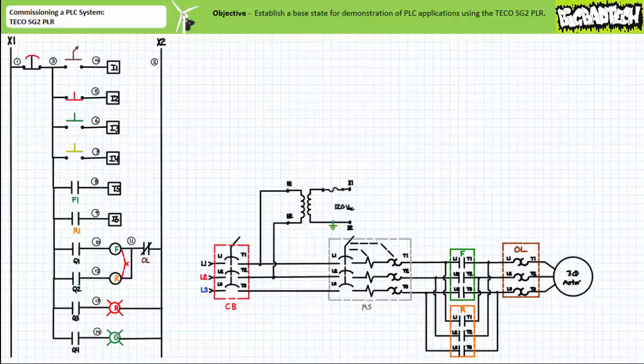Wired in this fashion, the normally closed overload contact serves as a means of overriding the program in the event of an overload. Electromechanical relay output Q3 energizes or de-energizes a red pilot lamp, and electromechanical relay output Q4 energizes or de-energizes a green pilot lamp. Again, note the maintained contact normally closed e-stop serves as a hardwired bottleneck through which all field output devices immediately downstream of it must also negotiate to be energized. Wired in this fashion, the hardwired e-stop directly upstream of all field output devices effectively severs all outgoing communication from the PLC without the necessity of resorting to any programmed instructions to do so.